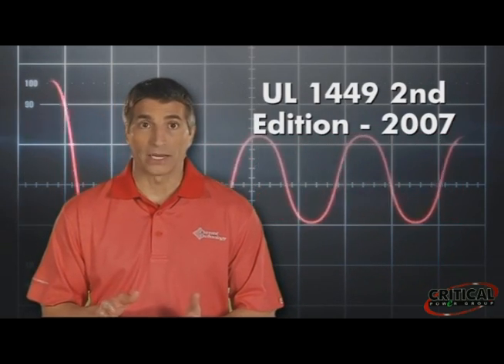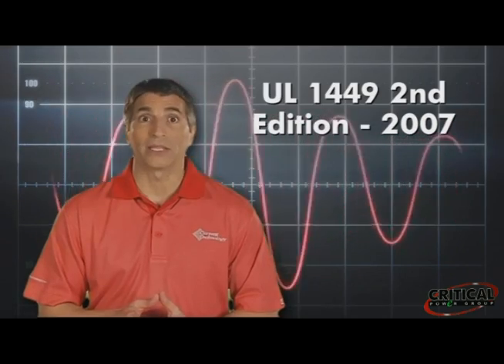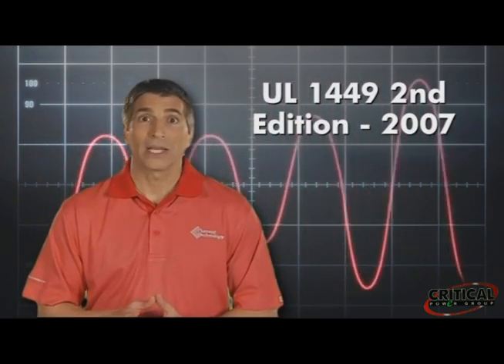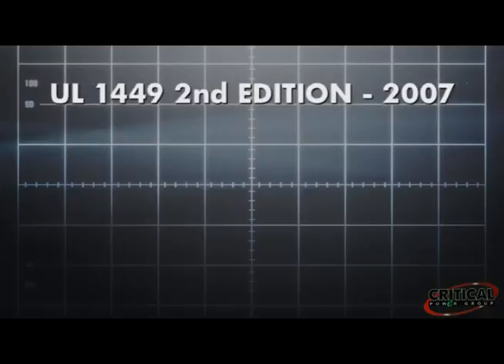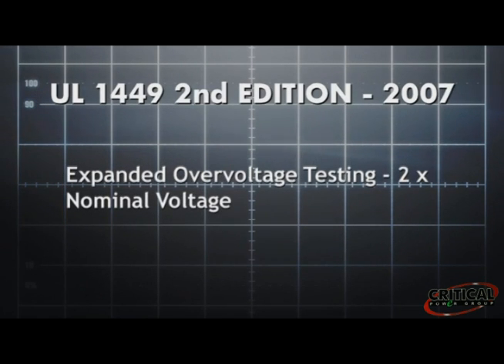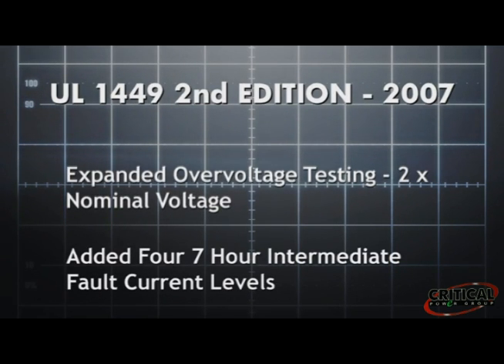UL 1449, an Underwriters Laboratories document dealing with the safety of SPDs, has undergone some recent revisions. UL 1449 second edition, which became effective in 2007, primarily focuses on ensuring SPDs fail in a safe manner. All products were subjected to 2 new tests, an expanded overvoltage test and an application of 4 different limited currents to ensure that the unit under test either stabilized its temperature safely or that it took itself offline safely by blowing some sort of fuse or tripping a breaker.